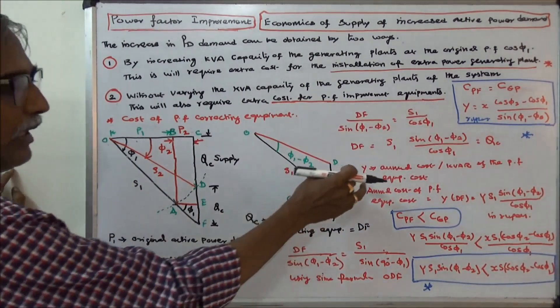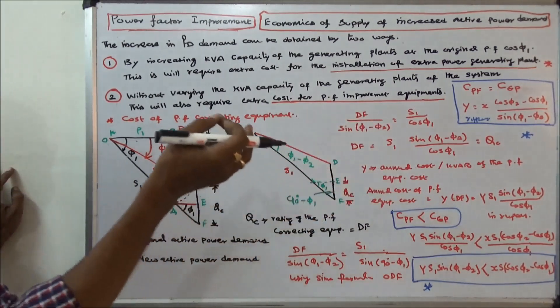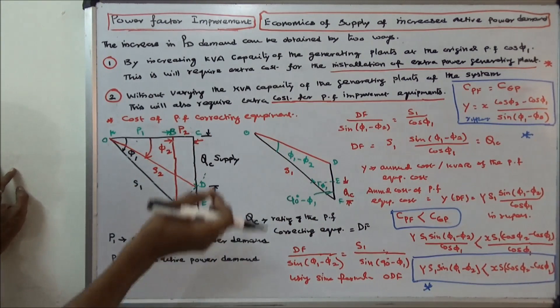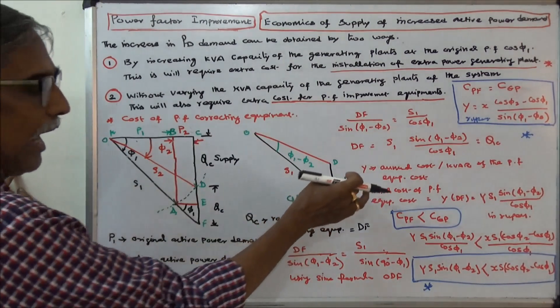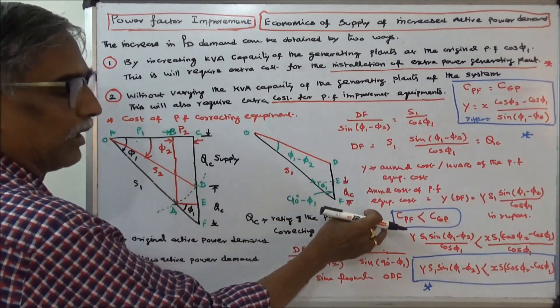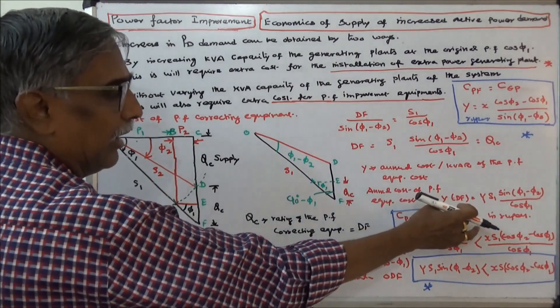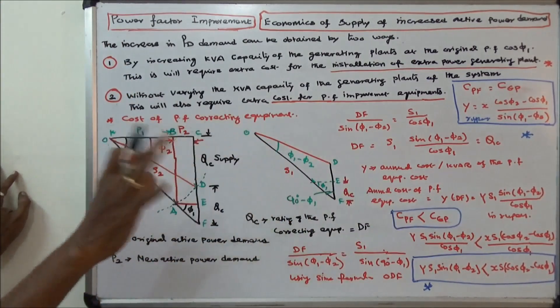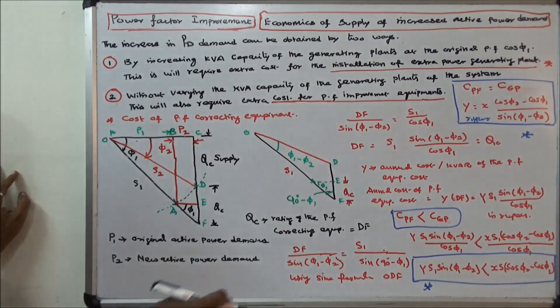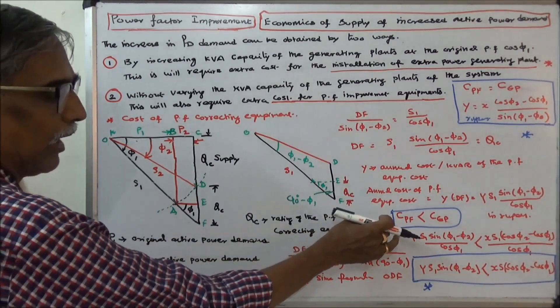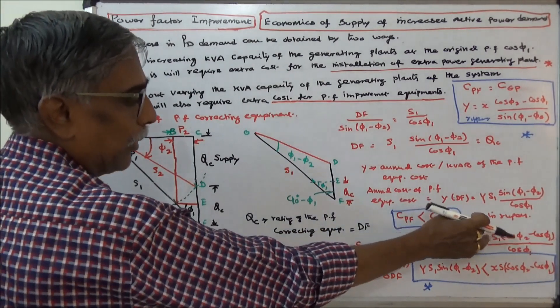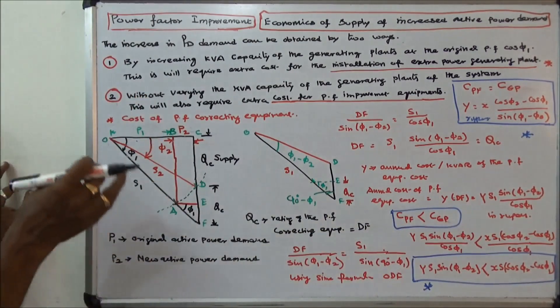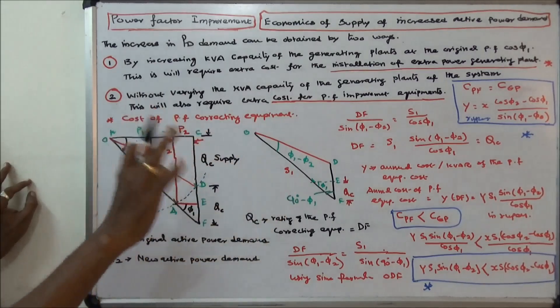Let Y be the annual cost per kVAR of the power factor correcting equipment. Therefore, the annual cost of the power factor equipment is equal to Y into DF, that is, Y into S1 into sine(phi 1 minus phi 2) divided by cos phi 1. The cost of the power factor equipment should be less than the cost of the generating plant.